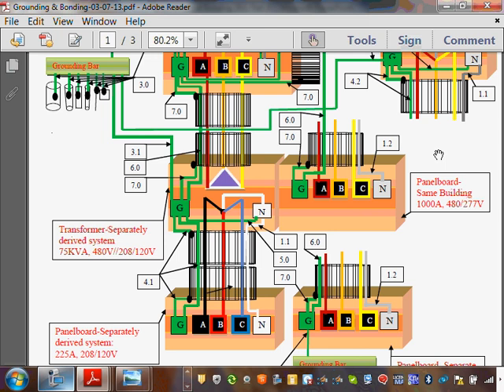If you don't have these two, you have to pull a grounding electrode conductor from wherever this transformer is sitting, all the way to where? To the grounding electrode system inside your building.